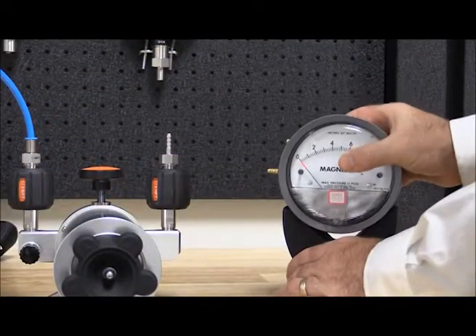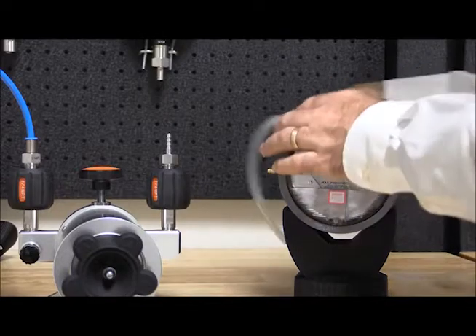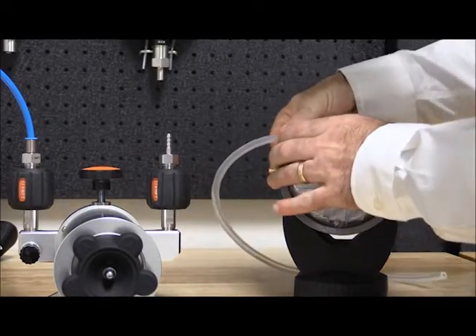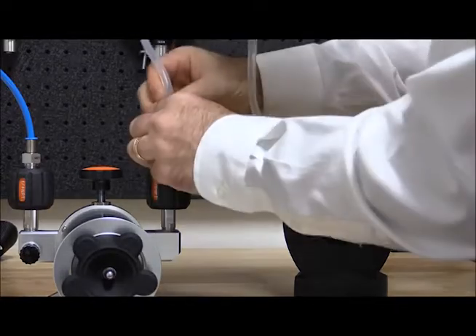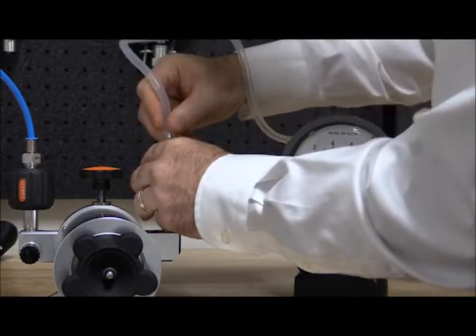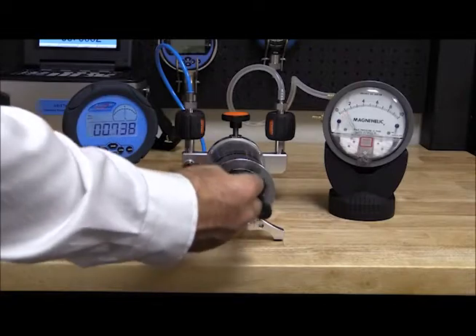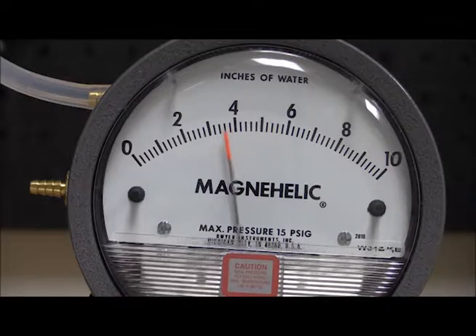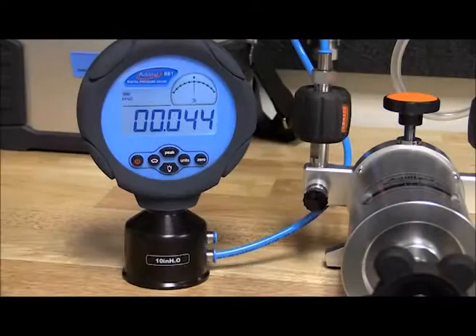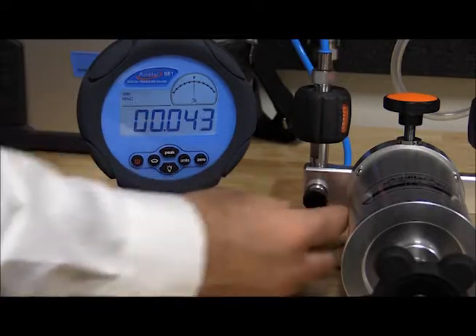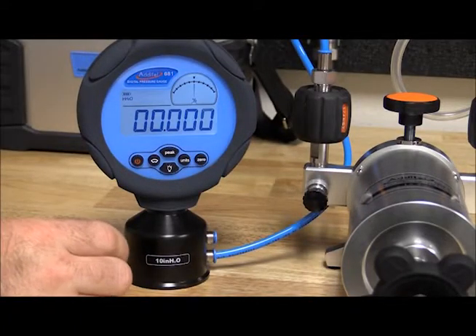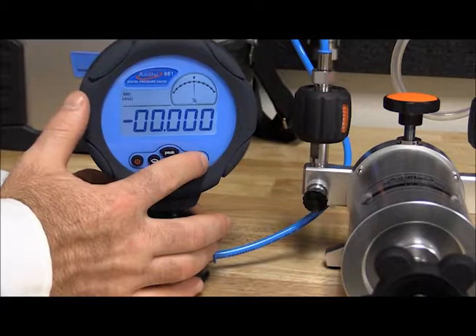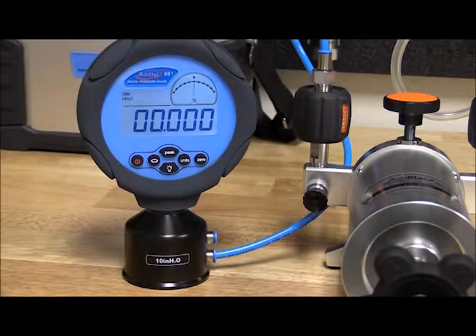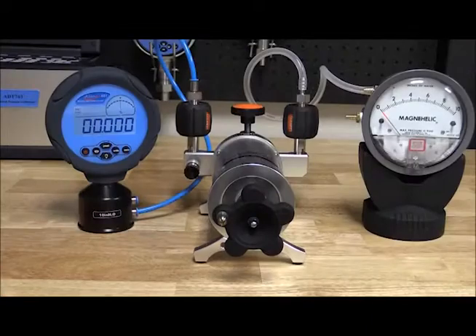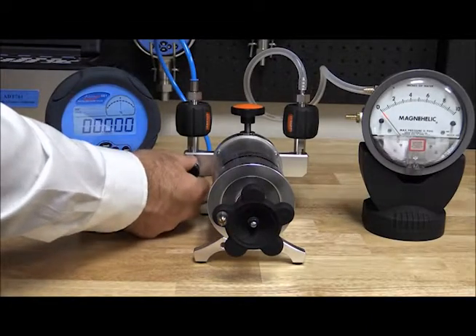It is important that the DUT is in the proper orientation based on its application use. This gauge was calibrated and used in a vertical position, so we will calibrate it in the same orientation. For many analog gauges, it is good to exercise the gauge to its full scale 1 or more times prior to taking calibration points. First, we need to zero the reference. We could also zero the DUT if it allows for a zero. Because this is an analog gauge and is not normally zeroed in application, we will not zero the DUT for calibration. Now we are ready to generate pressure and record our results.